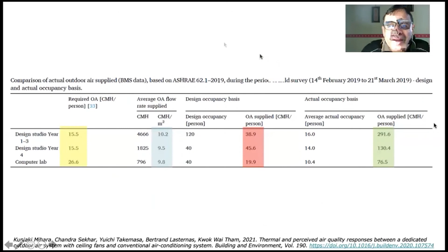So the studio years 1 to 3, which are on the DOA CF concept, show about a 30% reduction compared to the computer lab, which is our reference point. And year 4 is about 38.6%. At the computer lab reference point, the loads are high, or the cooling load or demand on the coil is high, for a variety of reasons, since the cooling coil is the place where the cooling needs to be done.